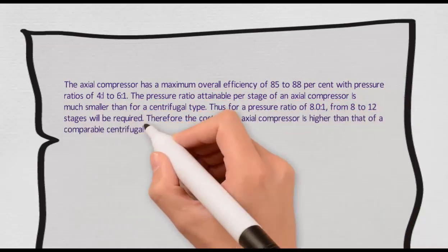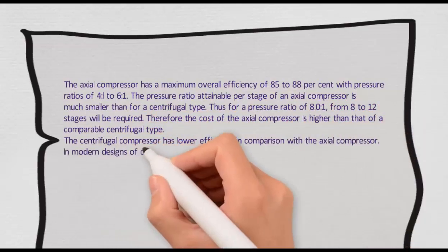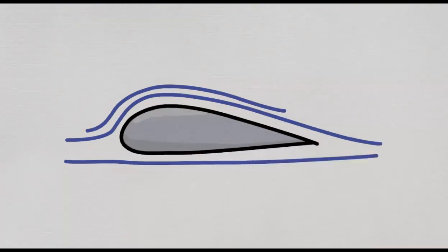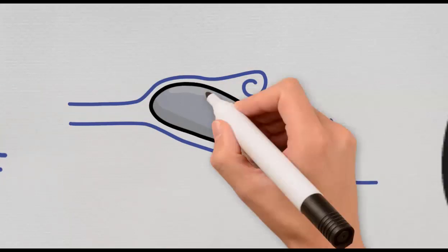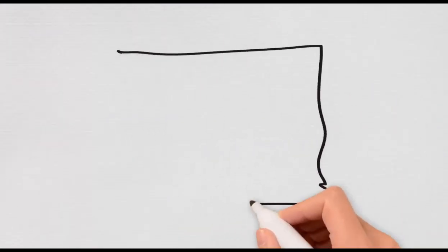The pressure ratio attainable per stage of an axial compressor is much smaller than for a centrifugal type. Thus for a pressure ratio of 8, from 8 to 12 stages will be required. Therefore the cost of the axial compressor is higher than that of a comparable centrifugal type.